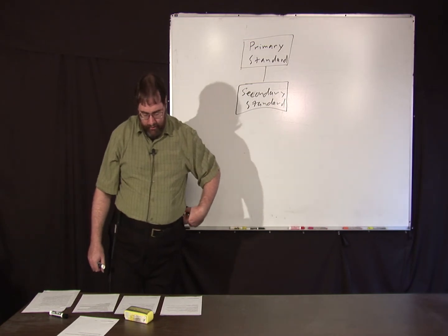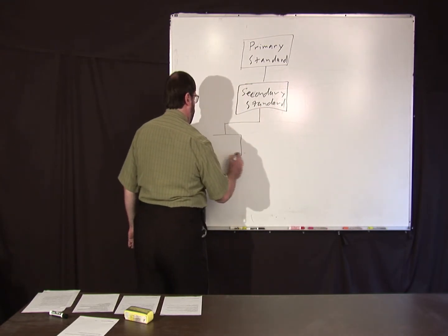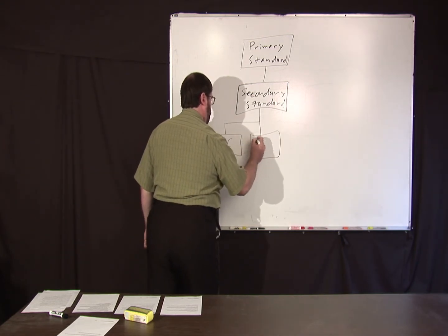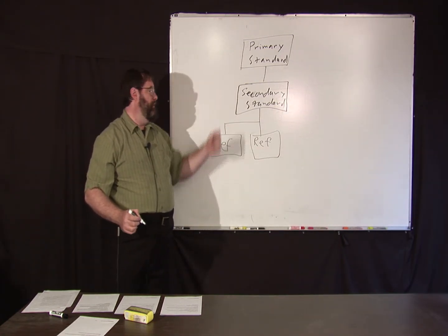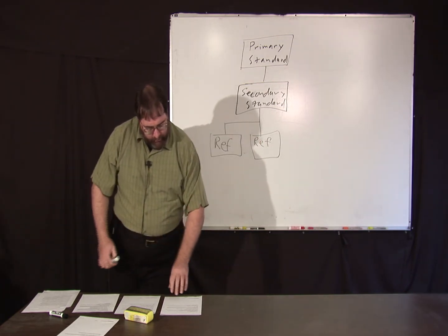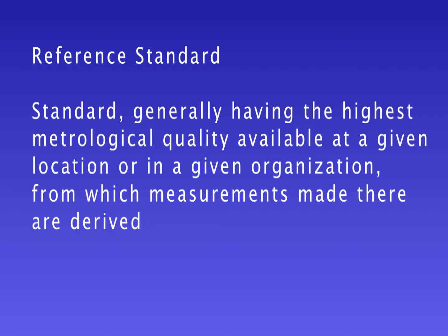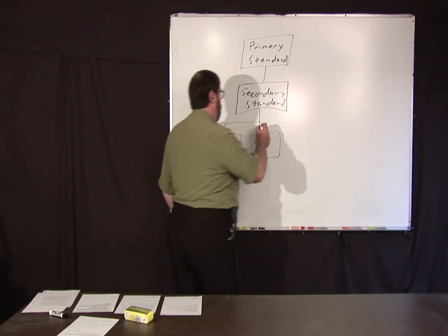And then there's lower-level standards that this might be used to calibrate reference standards, a whole bunch of them maybe. So, this might be, these might actually be done inside a national lab. This might be done in regional companies or something. A reference standard is defined as a standard usually having the highest metrological quality available at a given location or in a given organization from which measurements made there are derived. So, you have these reference standards out at other locations.